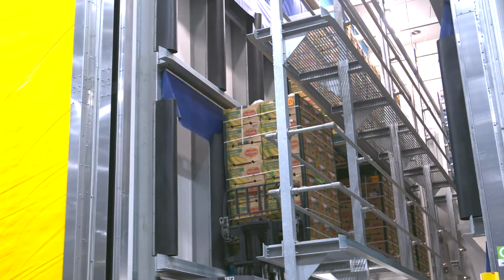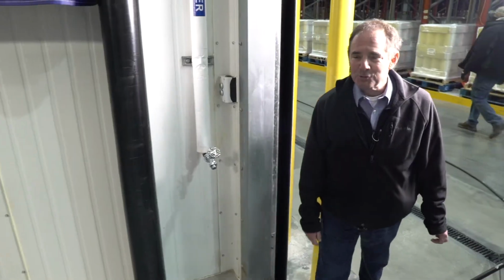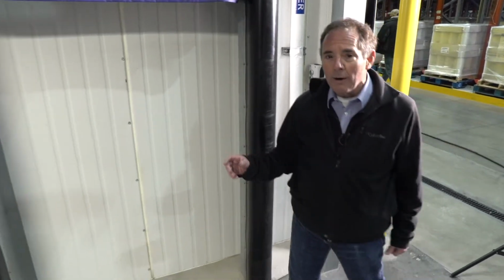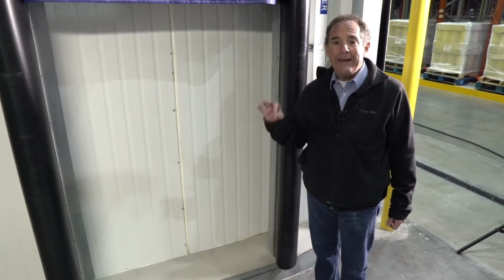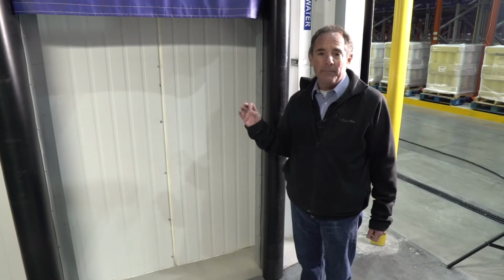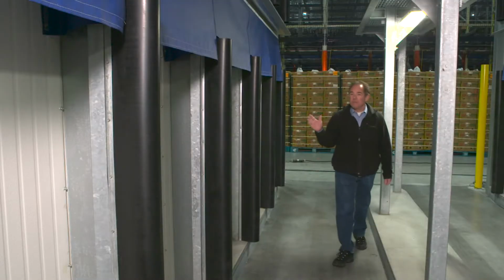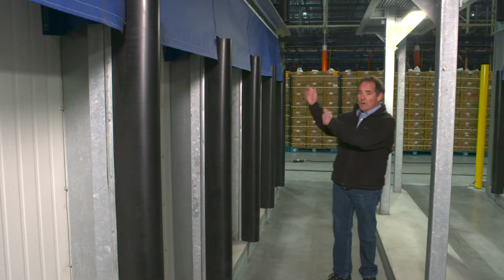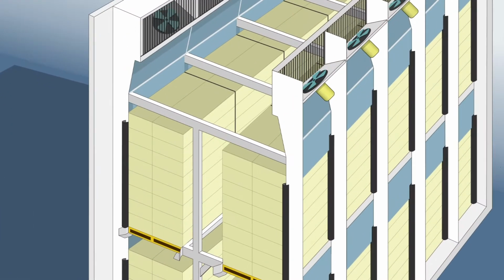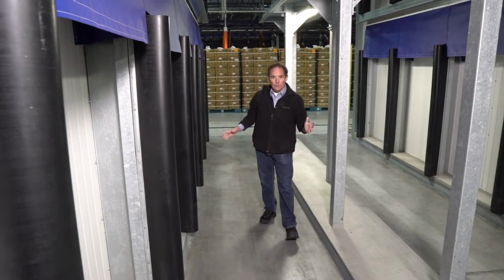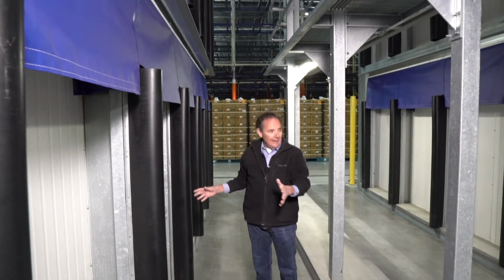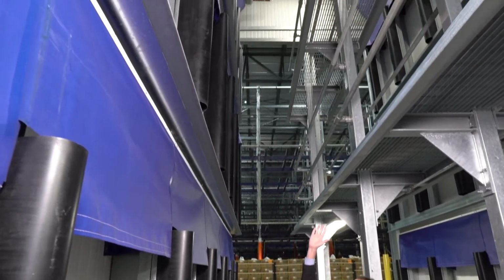First, let's take a look at the airflow enclosure system. So tarpless ripening rooms work by circulating temperature-controlled air evenly throughout every box in the ripening room. Every room is made up of a series of vertical air circulation cells with a forced air fan at the top. In this room, there are 7 cells on each side, and each cell is 3 pallets high.